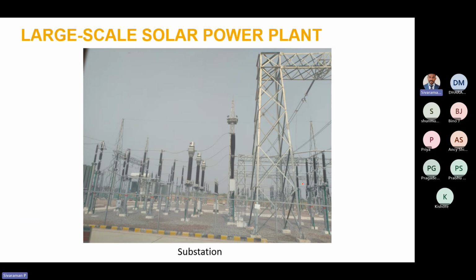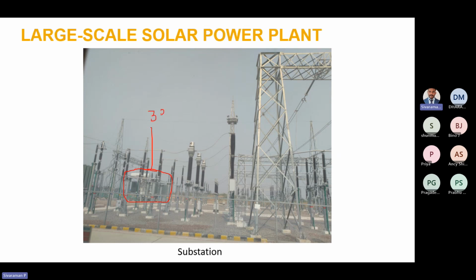So this is the view of the substation. The backside, what you are seeing here is the power transformer. The power transformer is connected on one side at 33 kV, and the outgoing side is 230 kV. Let's consider 230 kV. So these are 230 kV equipments. This is a CT, current transformer. There will be a switch gear for this also. Mostly for high voltage applications we will use SF6 based switch gear. This is an SF6 based switch gear.